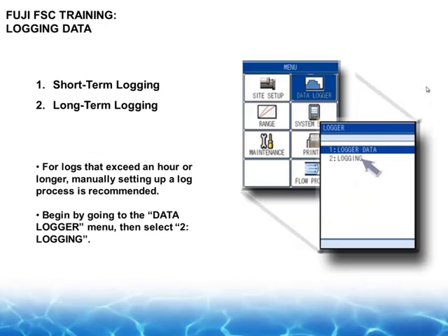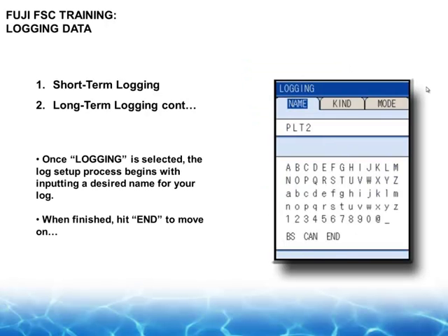Now if you want to set this up for a short-term or a long-term log, we need to go in and program the meter with the start and stop time and what you'd like to log. So we go back into the menu, and now we go to the data logger tab, and under the data logger tab we select number 2, logging. Here we traditionally use a 2 gig or larger SD card, which basically means you can store millions of records. Millions. You can store data from now, once a minute, to 6 or 9 months out. So you don't have a storage problem.